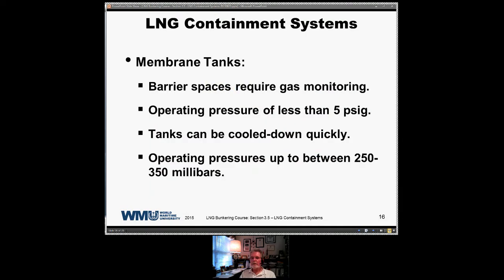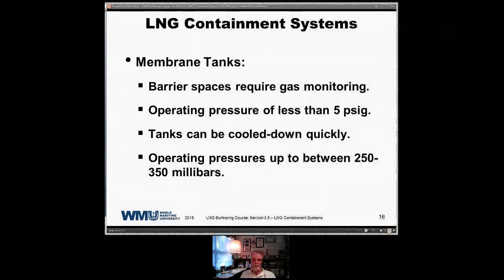The barrier spaces require gas monitoring, and they are monitored 24 hours a day, 7 days a week by your gas detection. The operating pressure of this type of tank is less than 5 psig. Tanks can be cooled down quickly. This is one of the advantages of a membrane tank. Since the material that the tank is constructed of is so thin, you can cool them down very, very quickly, and that's done by spraying LNG into the tank through a series of spray nozzles. And once the temperature of the material inside the tank is approximately minus 130 degrees C, you can then begin loading liquid in.